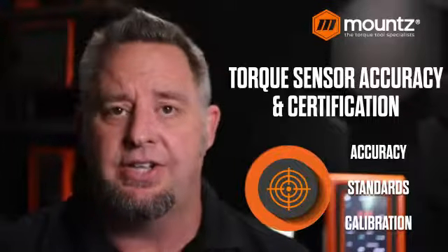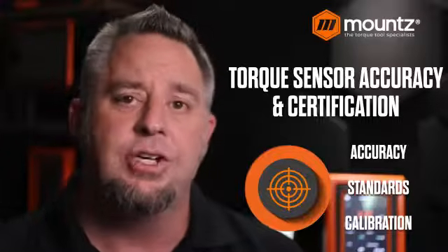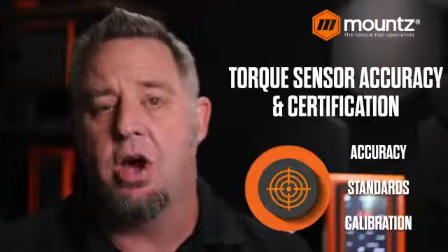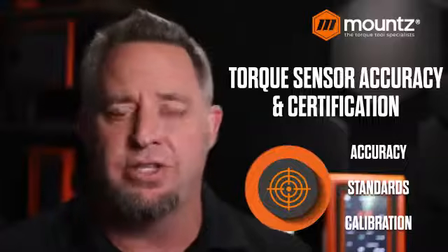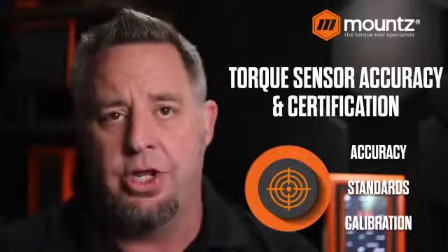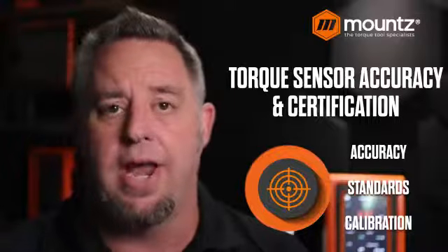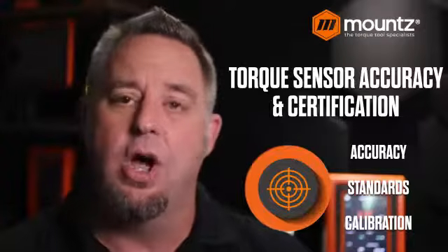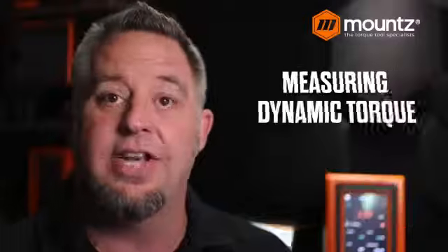You have the ANSI Z540 and the ISO 17025 certification for those sensors, and they do need to be calibrated on a frequency basis, either 6 months, 12 months, or depending on the usage, how you would like that sensor to be calibrated with your analyzers. So that's how the accuracy works in conjunction with the analyzers and the sensor itself.